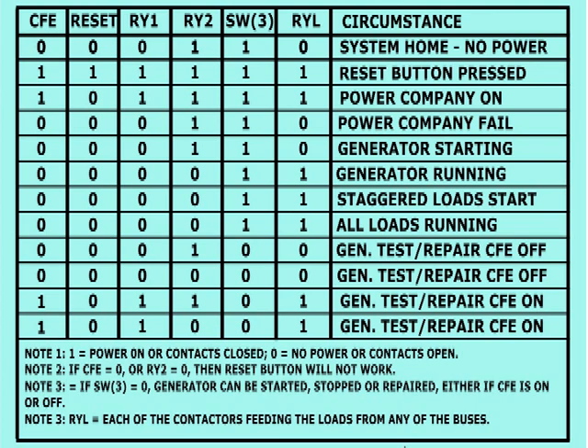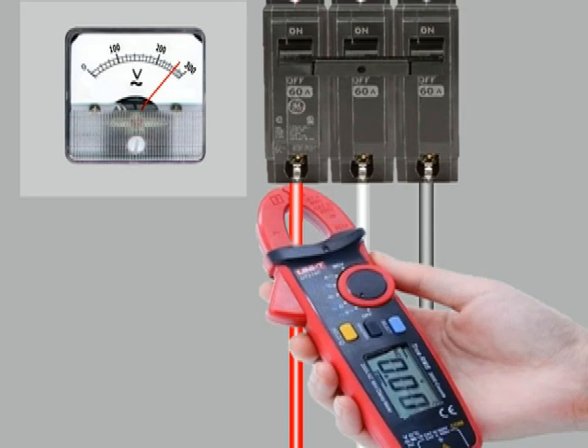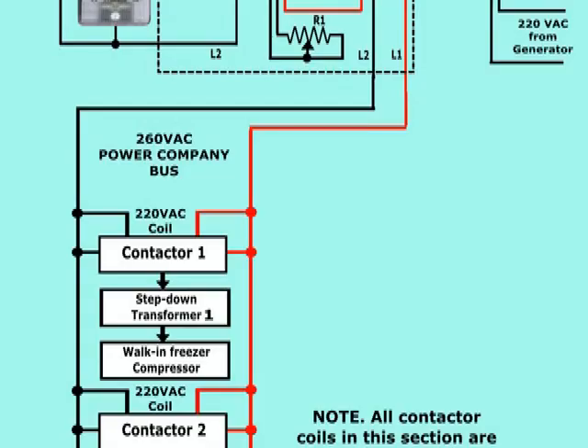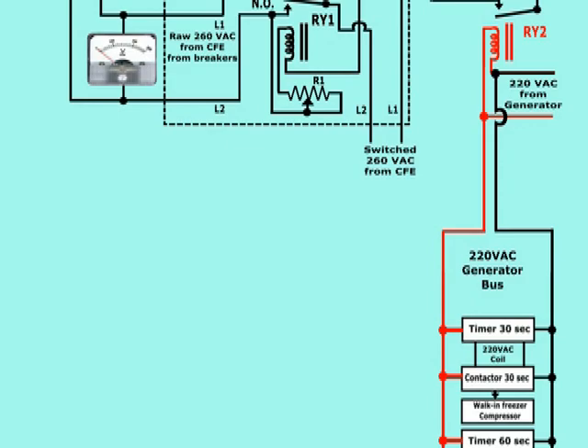If generator maintenance tests or repairs are required, the triple breaker switch is turned off manually, which disconnects the two phases of the generator from its branch, while making the stop button independent from the generator, thus allowing tests whether or not there is voltage in the power network, without the possibility of an undesirable coincidence between the power company network and the local generator due to human error. In the next video we will talk a bit more about the protection circuits which prevent the simultaneous activation of both power buses.